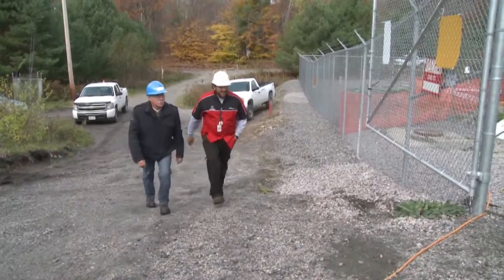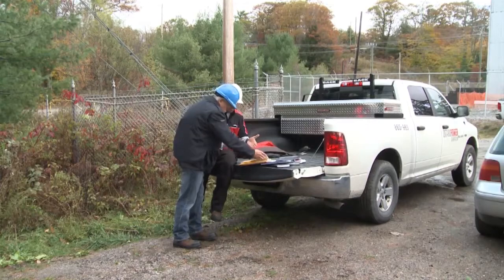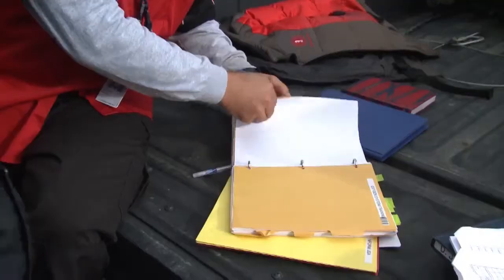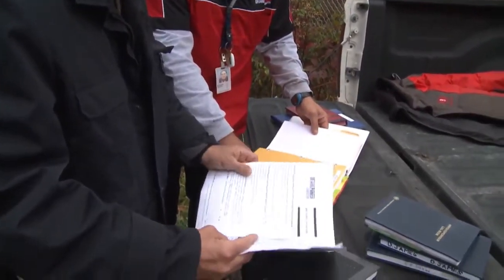When I arrive on site, I'm always looking for the diving supervisor. Afterwards, several documents will be reviewed: the operational plan detailing the scope of work, what procedures are going to be in place, lockout procedures, and differential pressure testing protocols and procedures — to ensure that there is no seepage or leakage within the dam structure itself.